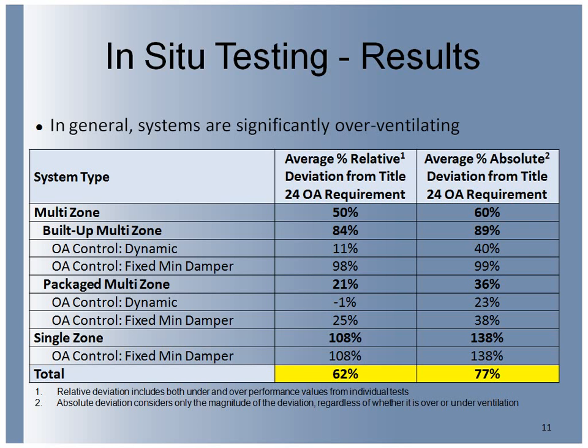And what we found was that in general, almost all the systems are significantly overventilating compared to Title 24 ventilation requirements, which we know in general for office buildings are even more than ASHRAE 62.1. So there's a breakdown here. The bottom line is we observed about 60% more overventilation compared to code than what was required. And then you can see some differentiation in there between the different types of systems. I think one of the interesting things, and we'll dig into these data a little more, but the single zone system, obviously the worst performer without any dynamic controls. But the packaged multi-zone systems, even with fixed damper positions, did a lot better than the built-ups.